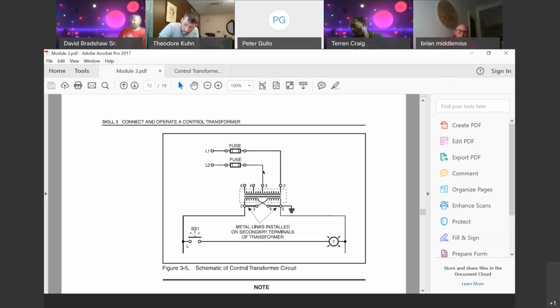So that's going to give us 208. We need 208 volts on the primary side in order for this transformer to give us 120 volts out on pin 2 and 5. Don't worry about pin 3 and 4 because they're internally connected in the transformer, there are metal jumpers inside already jumping that, you don't have to worry about it, okay?